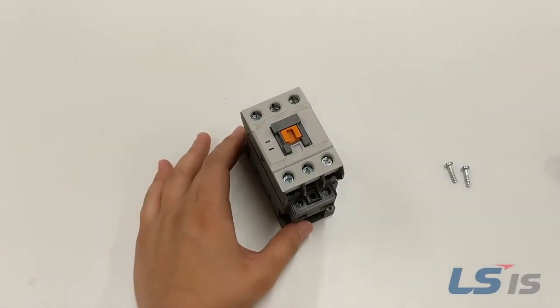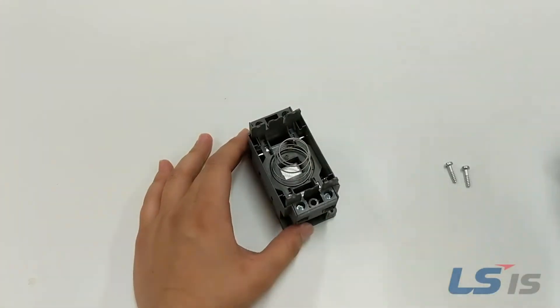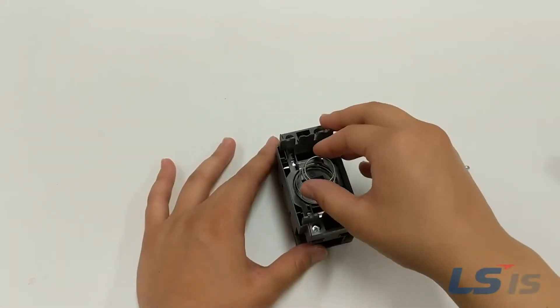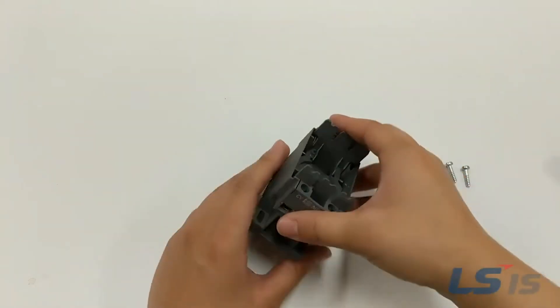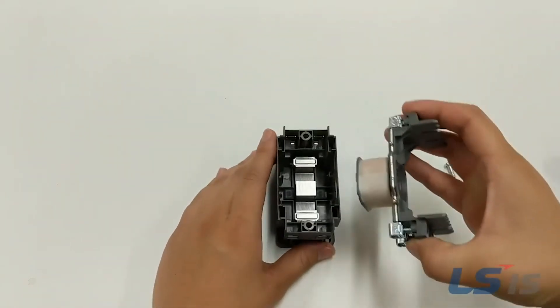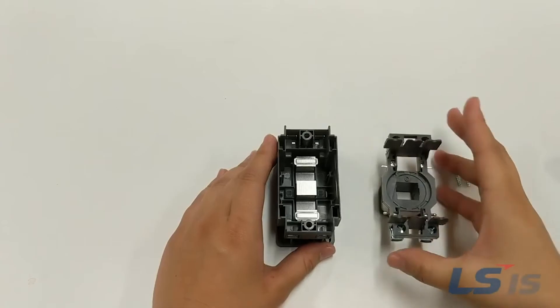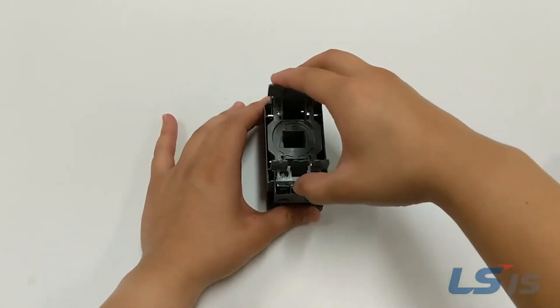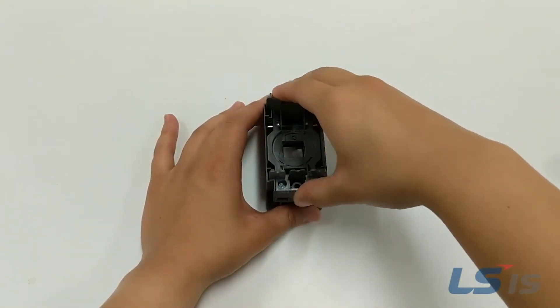Pull the top half off the bottom half and take out the spring. Then remove the coil by pulling up on both sets of A1 and A2 terminals. Install the new coil and place the spring back into the contactor with the larger end down.